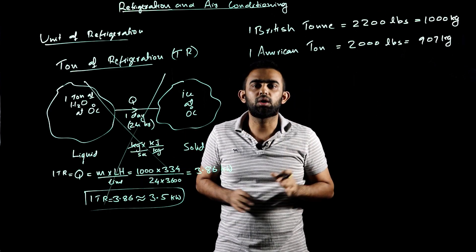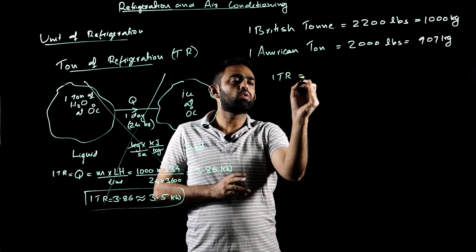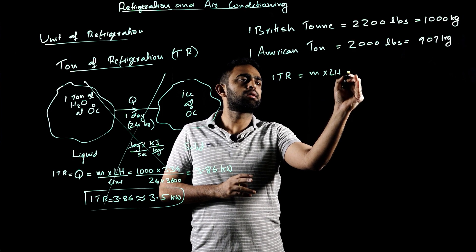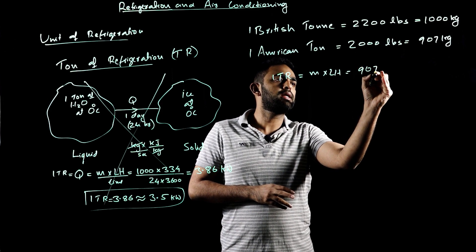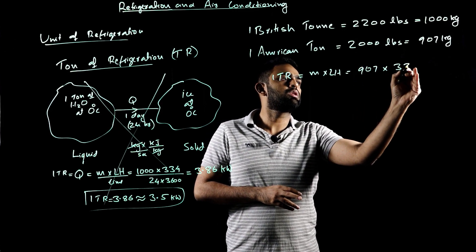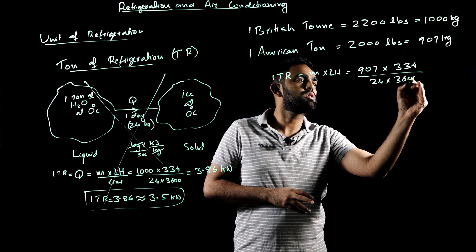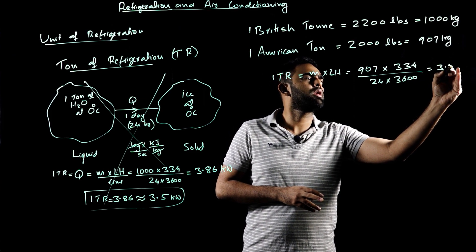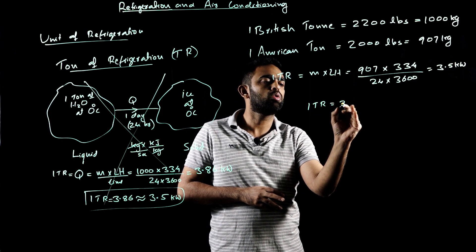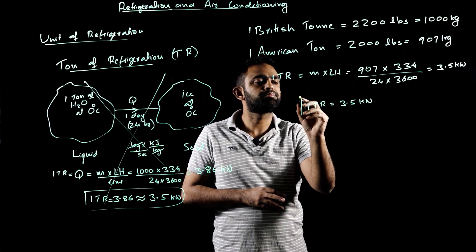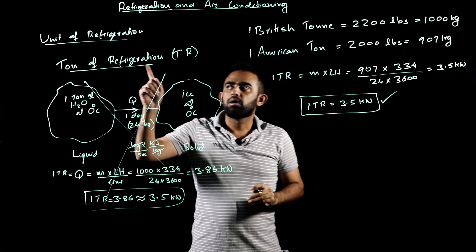For the American ton convention, 1 TR uses mass of 907 kilograms. So: 907 kilograms multiplied by 334 kilojoules per kilogram, divided by 24 hours converted to seconds (× 3,600), gives approximately 3.5 kilowatts. So 1 TR equals 3.5 kilowatts — this is the correct way of defining the unit of refrigeration.